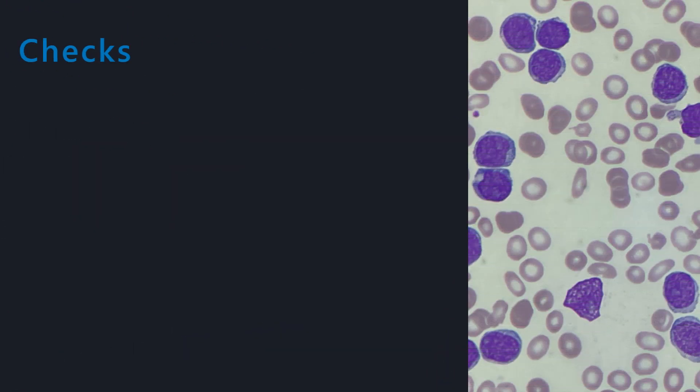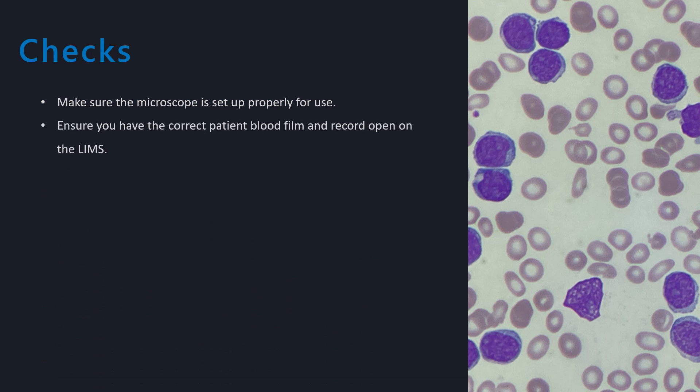Before we actually start the manual differential count, there are a few final things to check. Firstly, ensure that the blood film you're about to look at or perform the manual differential count on is the same as the record you have pulled up on the computer screen. Check the name and the sample identification number.